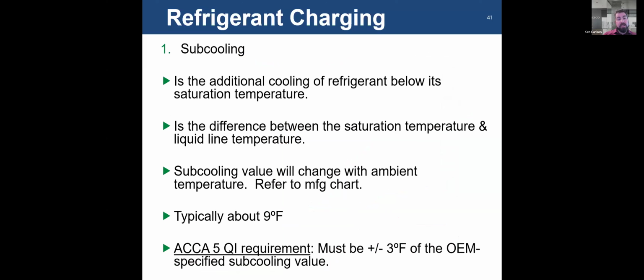So again, your subcooling value would change with ambient temperature. Refer to the manufacturer's chart. Typically 9 degrees. Don't use that for everything. Again, the manufacturer will give you what it requires at the given ambient condition. Again, per ACCA 5 QI, you should be within plus or minus 3 degrees.